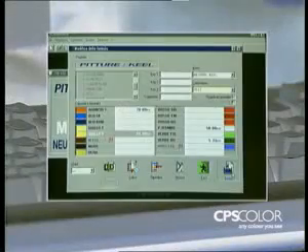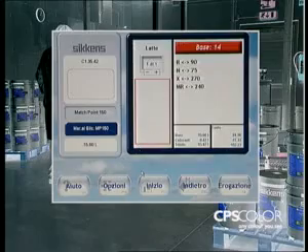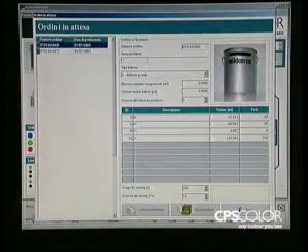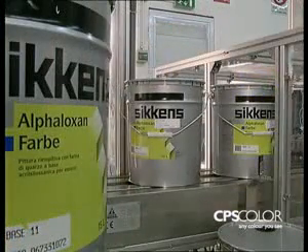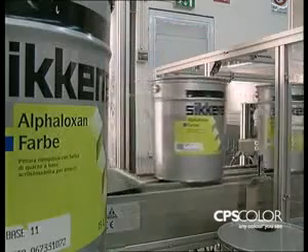Orders can be entered into the system by any software supporting the Corob F-Link protocol, either locally or via network. In this case, the operator is choosing the product and color to be produced for every order on the AkzoNobel Mix2Win software, which is then printing all the labels necessary for the cans to be produced. The order becomes active on the SCADA software as soon as the operator has entered the product mixing time and speed and acknowledged the base type to be used. As soon as the cans containing the bases are loaded on the stepped conveyor system, a can size recognition system checks that the size of the loaded cans matches the size required by the production order, warning the operator in the case of a mismatch.